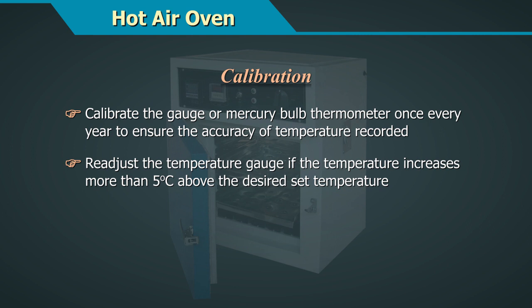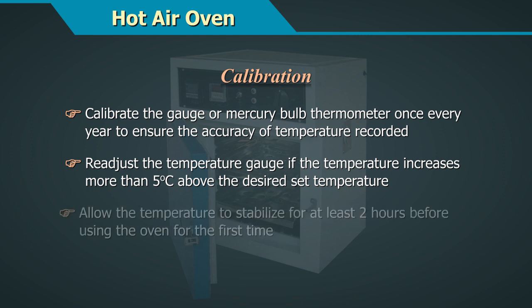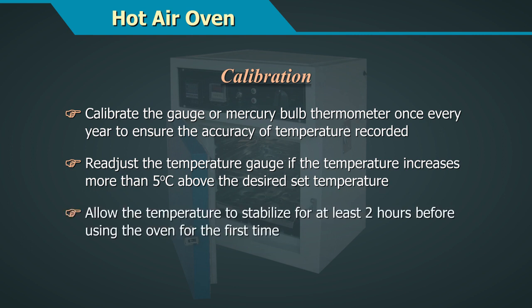Calibrate the gauge or mercury bulb thermometer once every year to ensure the accuracy of the temperature recorded. Re-adjust the temperature gauge if the temperature increases more than 5 degrees centigrade above the desired set temperature. Allow the temperature to stabilize for at least 2 hours before using the oven for the first time.